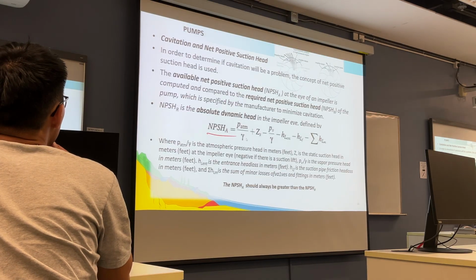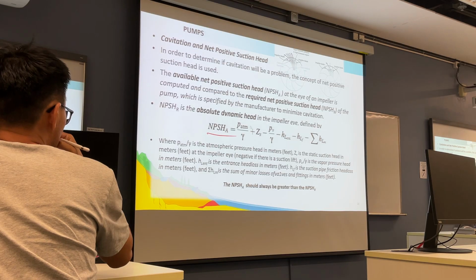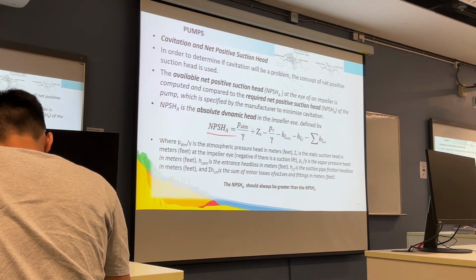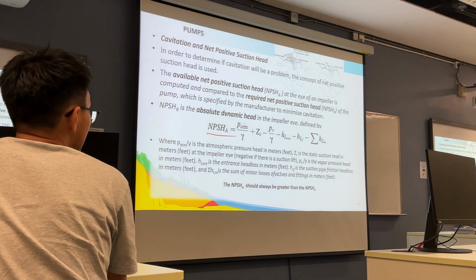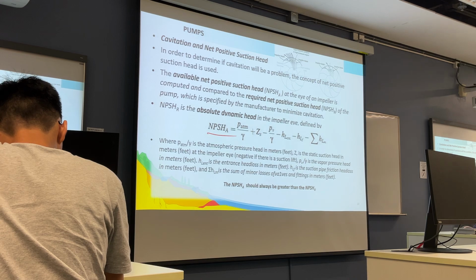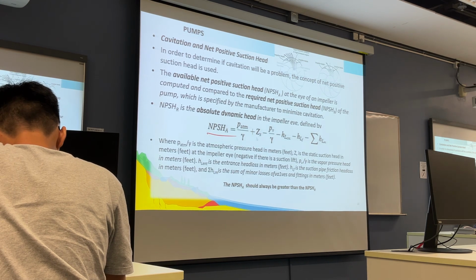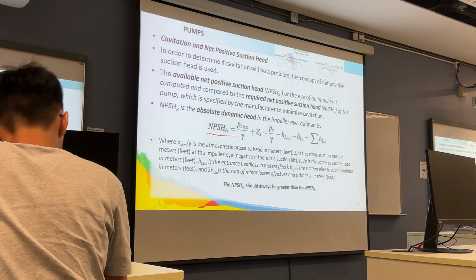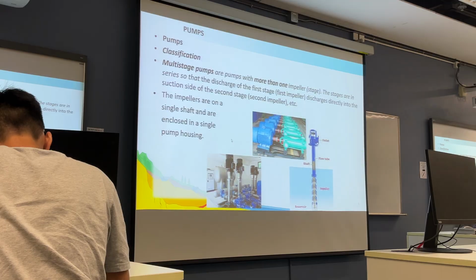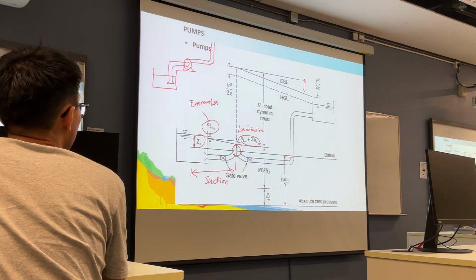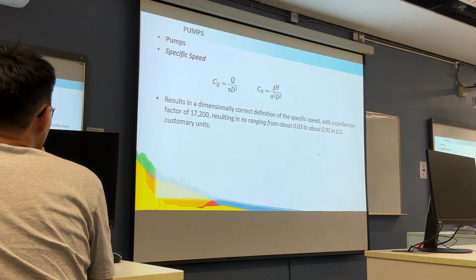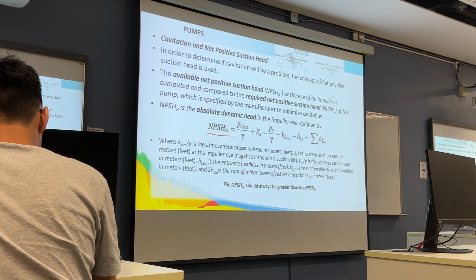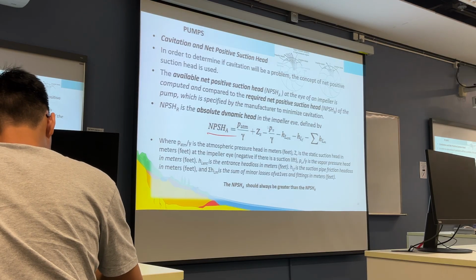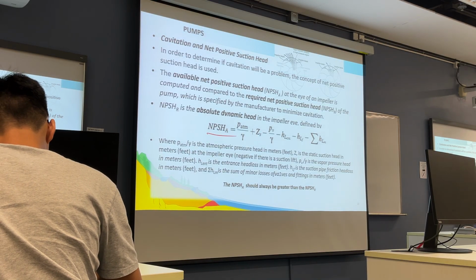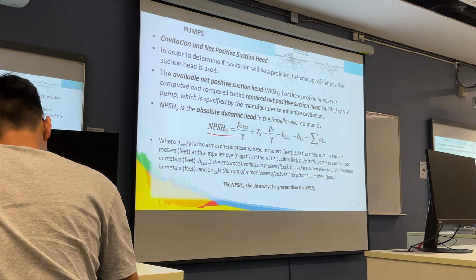The net positive suction head is calculated by P_ATM over gamma. This is the absolute atmospheric pressure head. Z_S is the elevation, the difference of the lower reservoir surface to the pump eye. Okay, this location, Z_S. This is usually a positive number, okay? And then P_V over gamma. P_V is the vapor pressure at the certain air pressure condition, okay?